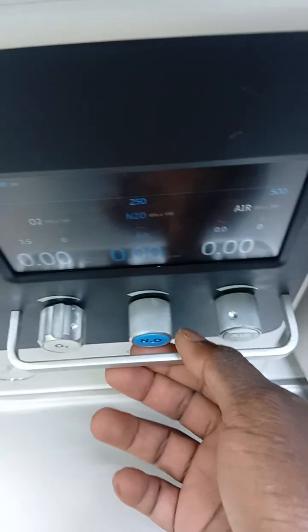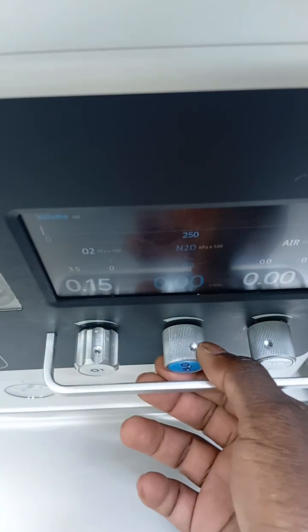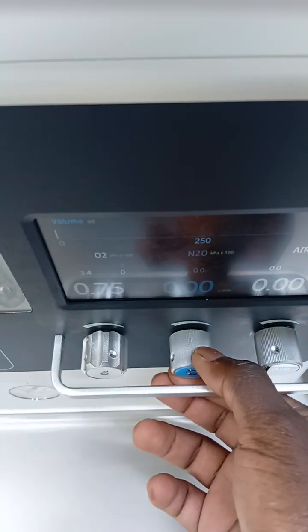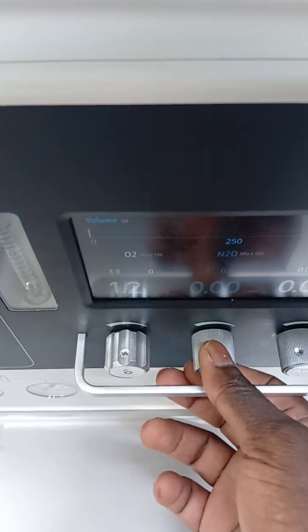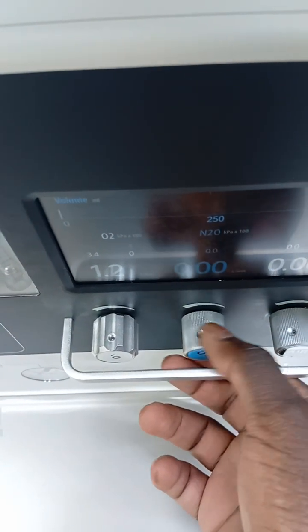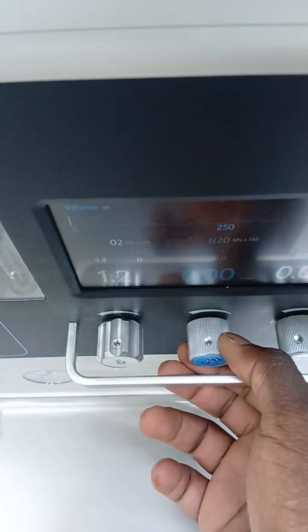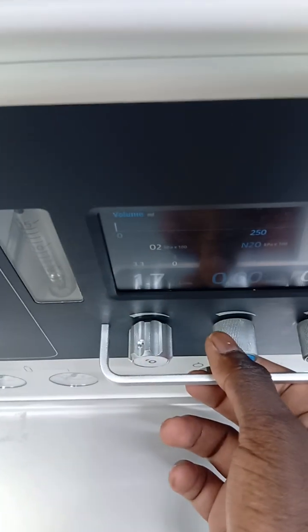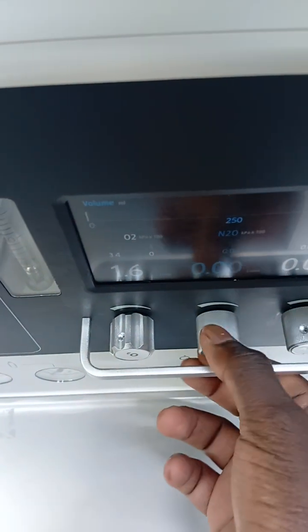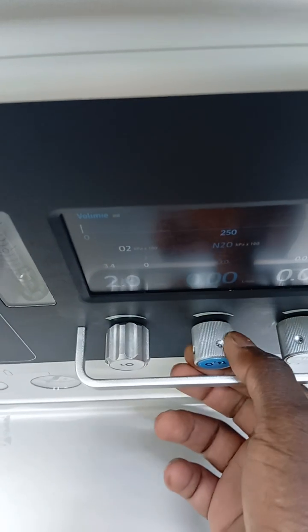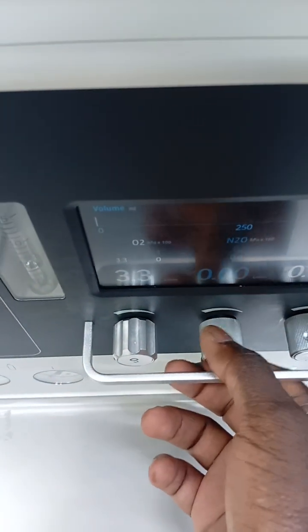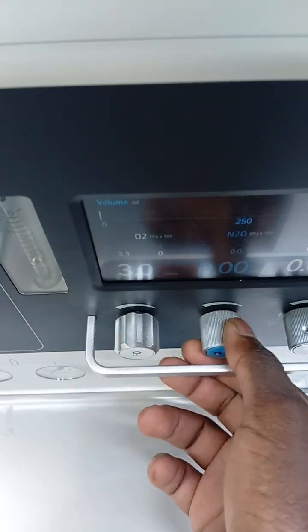And next to the oxygen is the nitrous. As you can see, as I rotate the nitrous, it is going together with the oxygen. This is called a hypoxic guard. It helps to prevent a patient getting a hypoxic mixture. It makes sure that the patient does not get less than 30% of oxygen. Remember, the air we are breathing is 21% oxygen. So this hypoxic guard is a safety feature that has been added by the manufacturer to make sure that anytime you put nitrous, it carries oxygen together. These are some of the features that have made anesthesia safe in this 21st century.